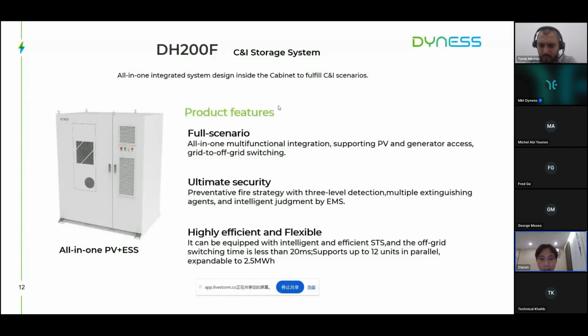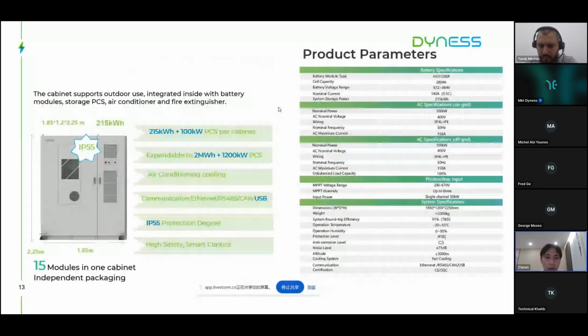So this one has inside a 100 kilowatt PCS and 215 kilowatt hour battery per cabinet. In most situations, you can expand it to 2.5 megawatt hour plus 1,200 kilowatt PCS. Inside there is an air conditioning cooling system, and besides all the communication we mentioned above, there are also USB communication ports, and there is an IP55 protection degree. So you can put it almost indoor or outdoor, any place you need on your C&I projects.